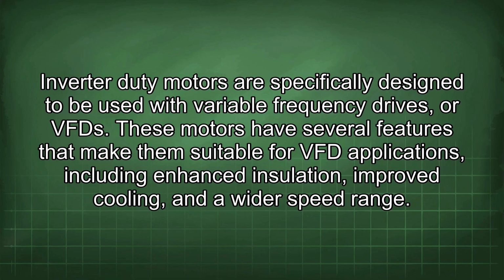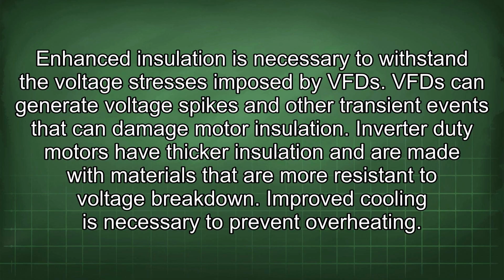Inverter duty motors are specifically designed to be used with variable frequency drives, or VFDs. These motors have several features that make them suitable for VFD applications, including enhanced insulation, improved cooling, and a wider speed range. Enhanced insulation is necessary to withstand the voltage stresses imposed by VFD. VFD can generate voltage spikes and other transient events that can damage motor insulation. Inverter duty motors have thicker insulation and are made with materials that are more resistant to voltage breakdown.